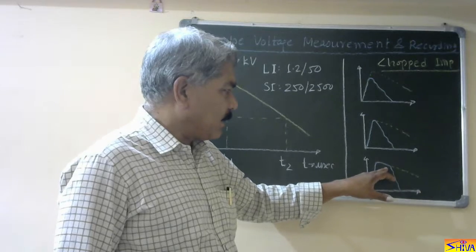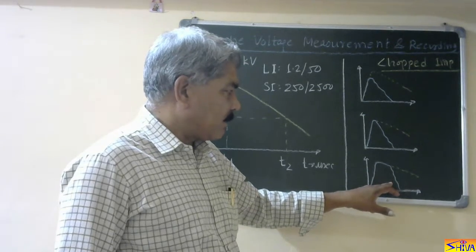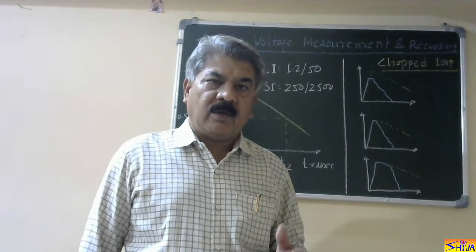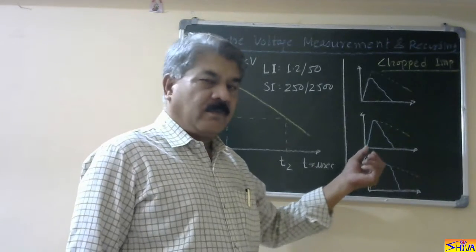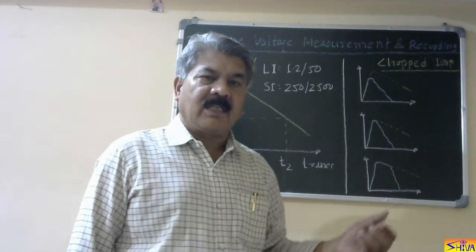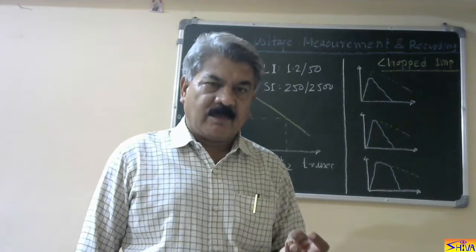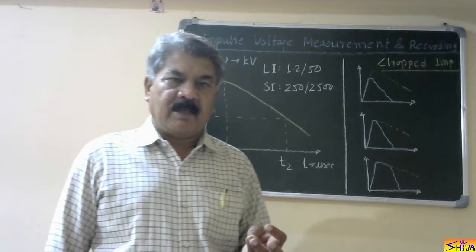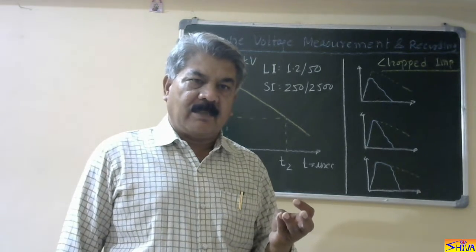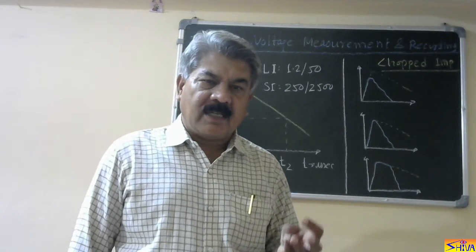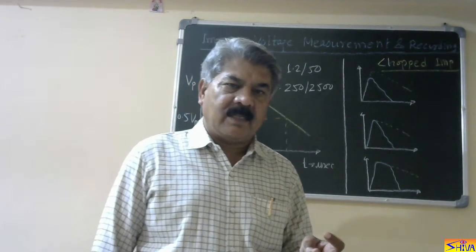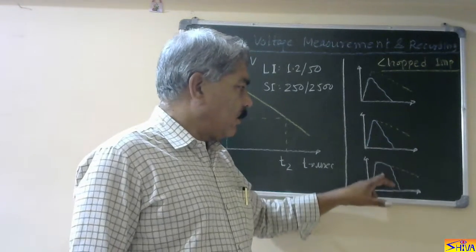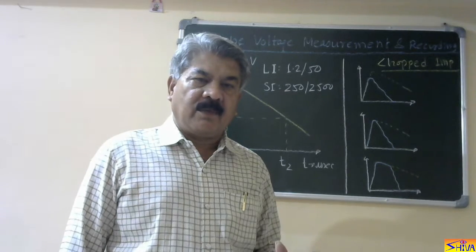So it has collapsed. Here it has taken place on the wave tail — it has collapsed. So in order to know the flash over point, spark over point, or the breakdown point on the impulse wave or the test object, it is necessary to record the impulse wave. First thing is, if flash over or spark over or breakdown does not take place, we must know whether the impulse wave is as per specification or not. Second thing is, if flash over of the object has taken place, then we must know the point of flash over — whether it is on the wave front, the peak value, or the wave tail. Therefore, recording of the impulse wave is necessary.